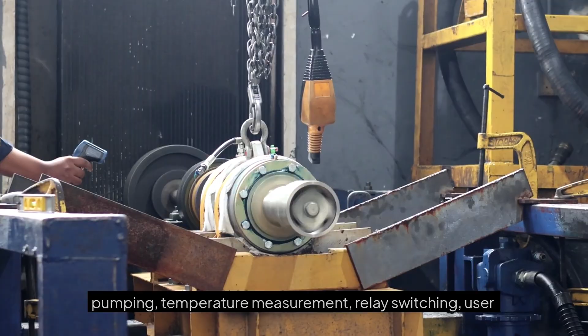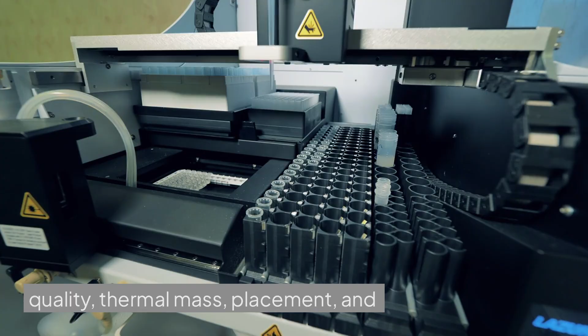Bench behavior alone is insufficient because heating, pumping, temperature measurement, relay switching, user inputs, indicators, and fault responses interact inside the appliance. Test conditions, safe boundaries, observation methods, and pass-or-fail criteria must be explicit. The temperature control path should use the relevant sensor type, placement, calibration approach, and fault states. NTC behavior can be influenced by contact quality, thermal mass, placement, and firmware filtering.